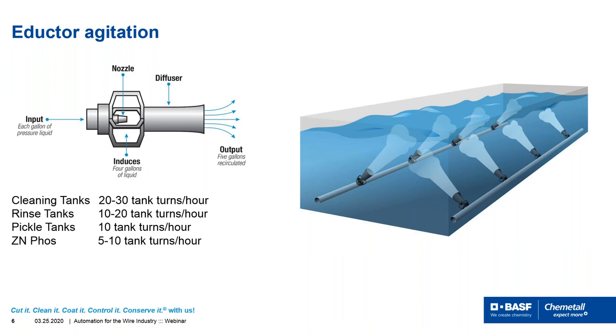The formula for this, if anyone's interested: take the gallons in your tank and multiply by how many tank turns you want, then divide by 60 since we're talking tank turns per hour, to reduce that down to gallons per minute. Then divide by five again. So for the 3,000 gallon tank with 25 tank turns, divided by 60, divided by five, we get approximately 250 to 260 gallons per minute for the pump we'd need.